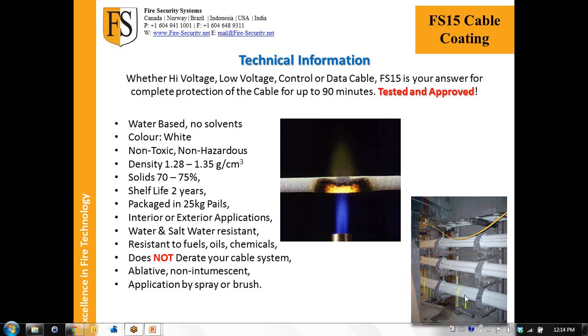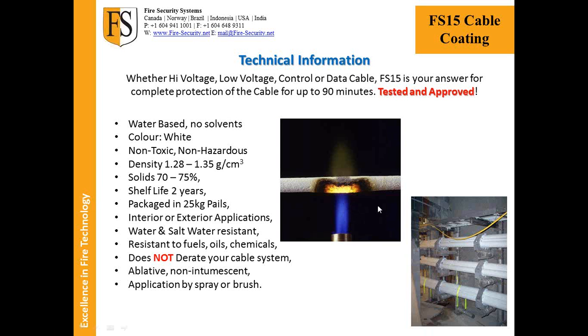Or if there's been a fire and the cable coating has activated itself, not unlike this area here within this picture. Once that flame's been extinguished, you may find that the area from here to here has been damaged, but the cable hasn't been damaged. You would pull away the existing cable coat and just repaint that area.